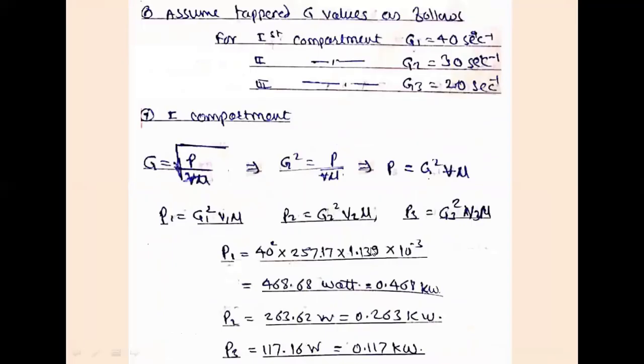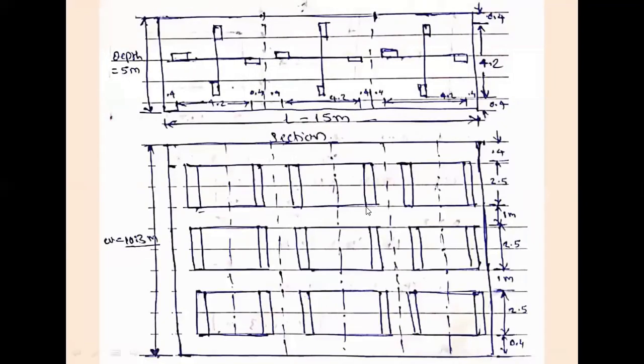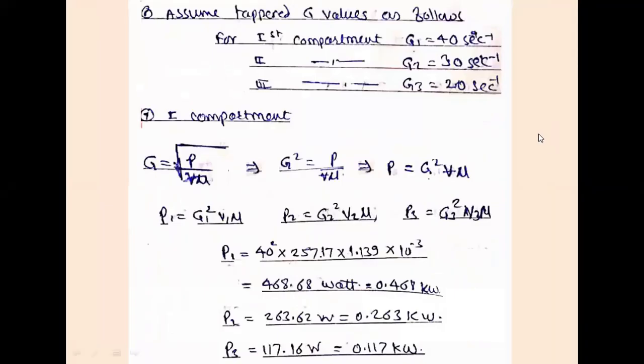Looking at the cross-section diagram, the total width of 10.3 meters is divided with 0.4 meters kept at the side, 1 meter clearance, and 2.5 meters for the blade length. The total depth arrangement includes 0.4 meters at top and 4.2 meters effective height. For the tapered flocculator, assume G values: G1 = 40 per second for compartment 1, G2 = 30 for compartment 2, and G3 = 20 for compartment 3.